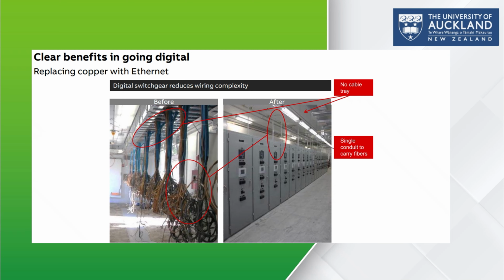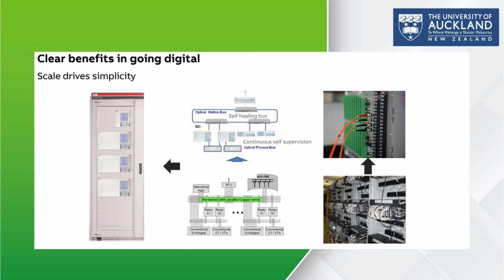On the left side, we have a modern digital protection and control cabinet. This integrates multiple relays and control units into one compact platform, reducing complexity, minimizing wiring, and improving overall efficiency. Now shift to the bottom center. Traditional substations still depend heavily on extensive copper wiring for relays, circuit breakers, RTUs, CTs, and PTs, which increases system complexity, and this creates a system that is harder to maintain, more prone to errors, and far less flexible.